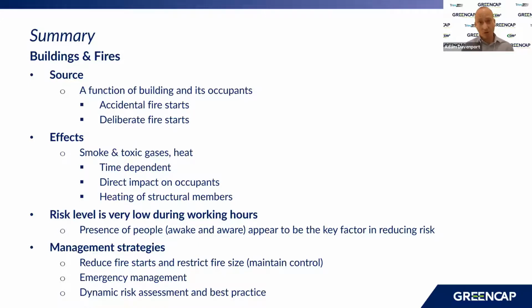Prevention is the best measure, obviously. We don't want to respond to emergencies if we don't have to. So checklists, gap analysis, inspections are so good to use to make sure we're preparing ourselves properly and preventing the emergencies from actually occurring. If we need to respond to it, training frequencies, making sure wardens are trained on a 6-monthly basis. That's in accordance with the Australian standards. Occupants are done at least annually, so general staff members or even just residents, they're told of the emergency procedures, reminded of them, because every building does different things.